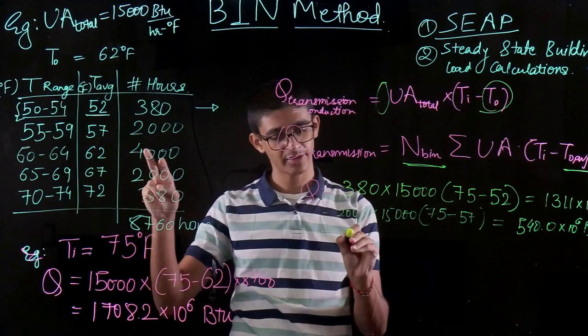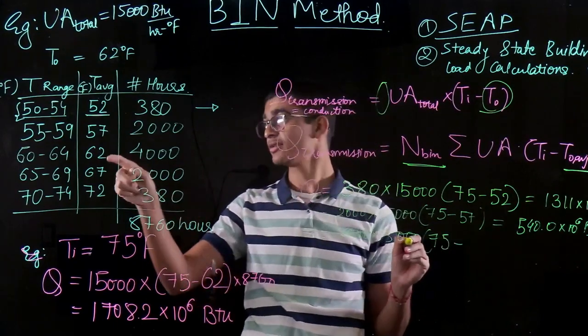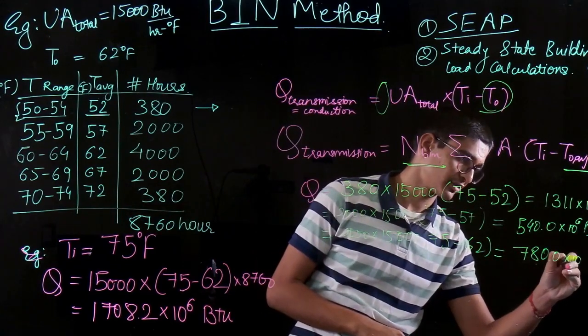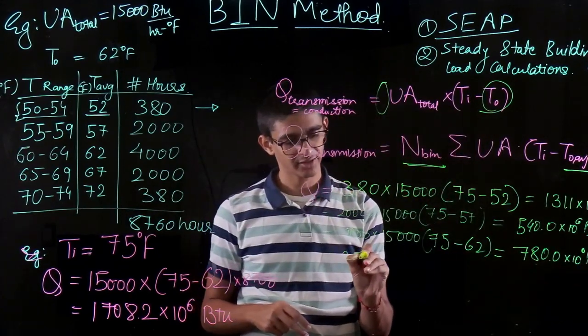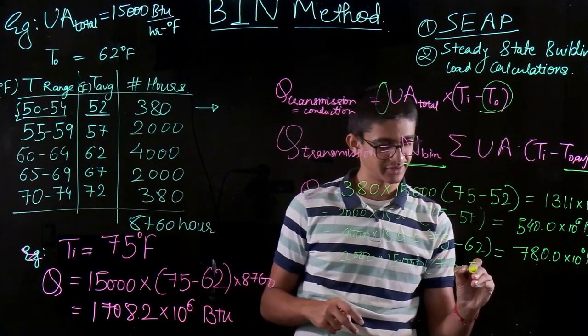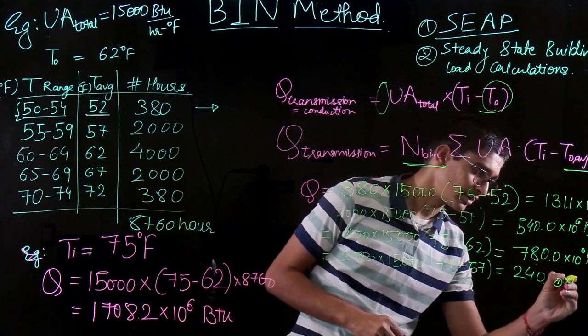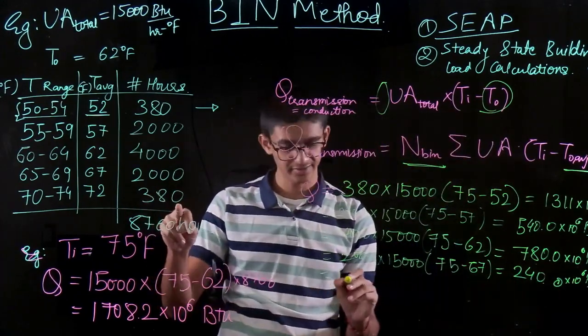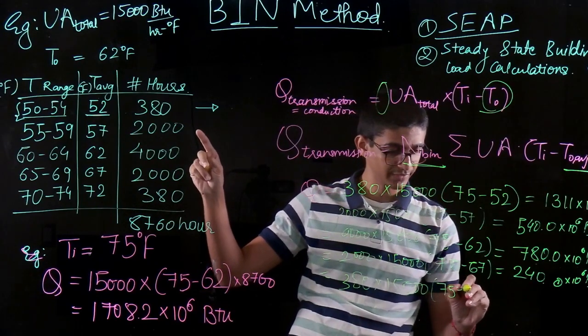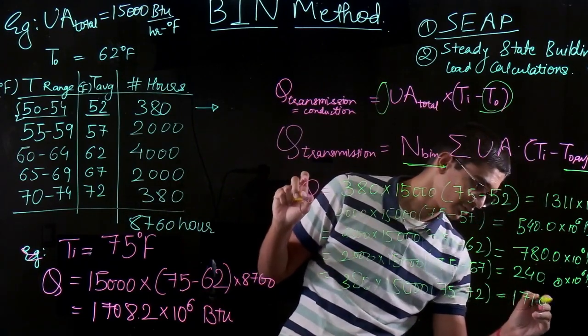Similarly for the third bin: Q = 4,000 × 15,000 × (75 − 62) = 780.0 × 10⁶ BTU. For the fourth bin: Q = 2,000 × 15,000 × (75 − 67) = 240.0 × 10⁶ BTU. And for the last bin: Q = 380 × 15,000 × (75 − 72) = 17.1 × 10⁶ BTU.